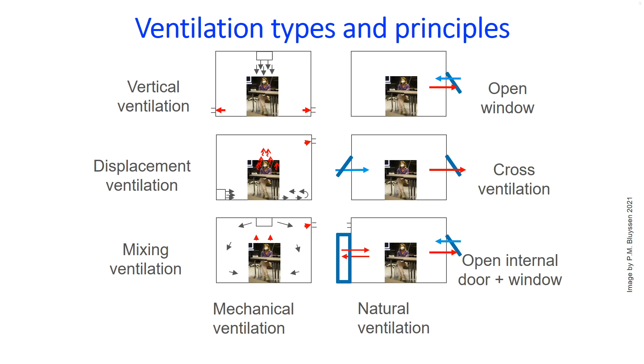Next to the type of ventilation, different ventilation principles can also be selected, such as mixing ventilation, displacement ventilation, cross ventilation, and personal ventilation. With mixing ventilation, air pollutants are diluted, reducing the number of infectious aerosols in the air. Displacement and cross ventilation move air horizontally or vertically through a space, replacing polluted air with fresh air. Personal ventilation supplies and/or exhausts air in the breathing zone of each person.